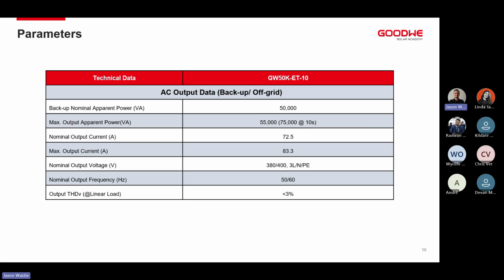If we've got massive inductive load startups using a transformerless or high frequency inverter, there are two different ways we can do it. The first one is obviously adding additional inverters to increase the amount of capacity that you've got. Just to note, I have 83.3 amps per phase, which means if we parallel the system and increase the system's physical size, we get more power output. That's quite self-explanatory. The second way, with a transformerless high-frequency inverter, would be using something like a VFD or VSD. A variable speed drive or frequency drive allows us to have a slower startup on these big inductive motors, and by doing that, we won't necessarily overload the system.